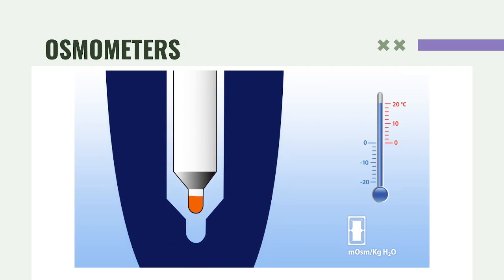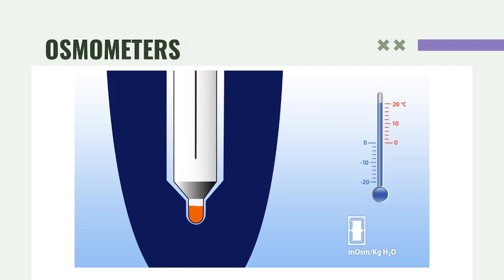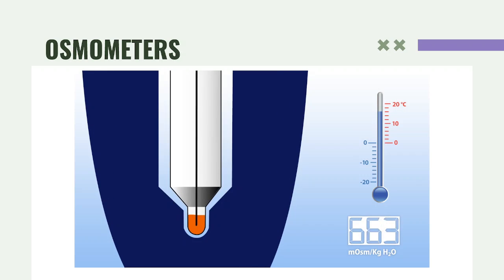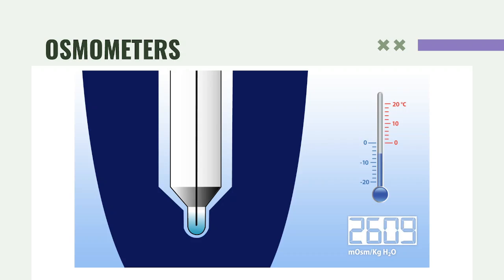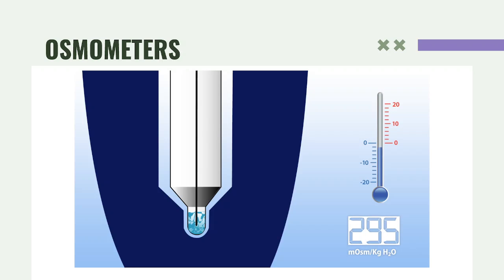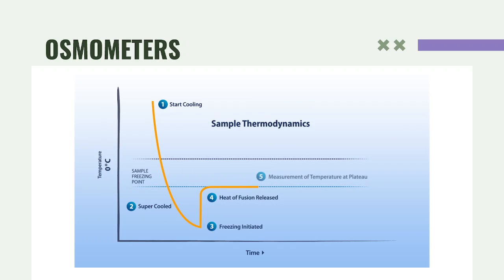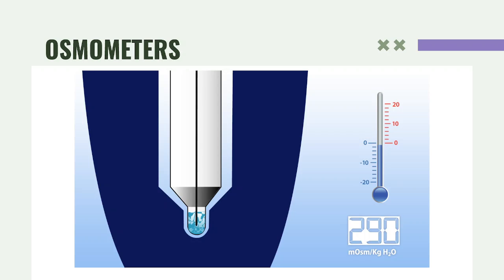Inside the osmometer, once a sample is introduced in the cooling chamber, it is rapidly supercooled to a temperature below the expected freezing point. A physical shock — the freeze pulse — is introduced, partially crystallizing the sample and forming an ice-water mixture around the temperature probe. The heat of fusion raises the sample temperature to a plateau where liquid-solid equilibrium is maintained. This temperature plateau represents the true freezing point; the osmometer measures it and calculates concentration in milliosmoles per kilogram of water.